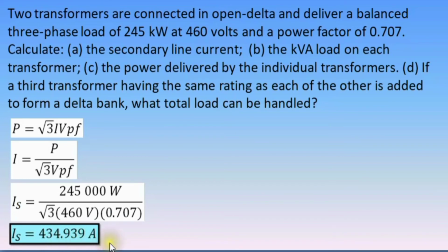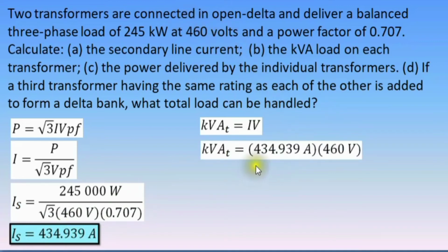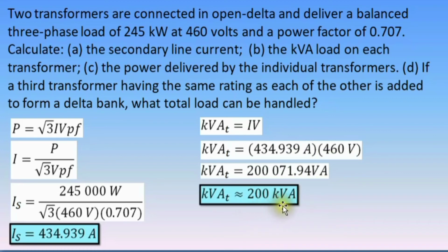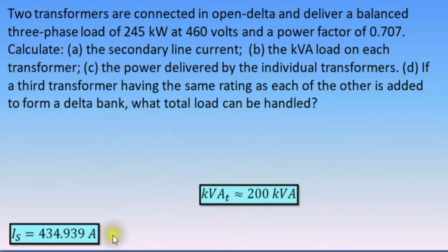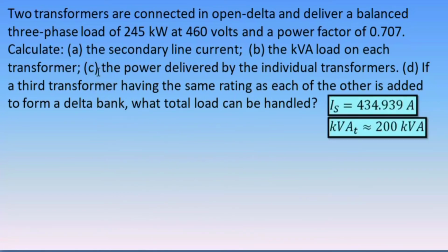434.939 amperes. Now let's go to letter B, the kVA load on each transformer. We are looking for the apparent power, therefore, we use this formula, current times voltage. Current equals 434.939 amperes and the voltage is 460 volts. Substitute those values. We have 434.939 amperes times 460 volts. The answer is 200,071.94 volt-amperes, or this is 200 kilovolt-amperes. Now that we have the answers for letter A and letter B, let's go to letter C. The power delivered by the individual transformers. So that is the effective power being delivered by each transformer.